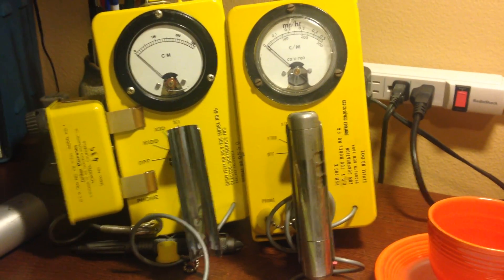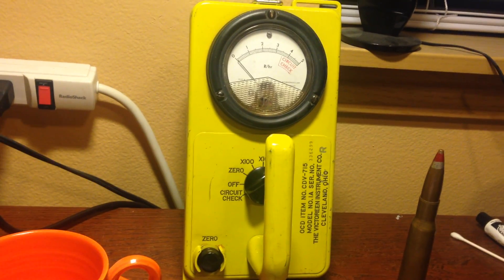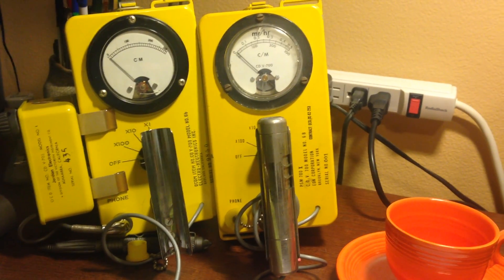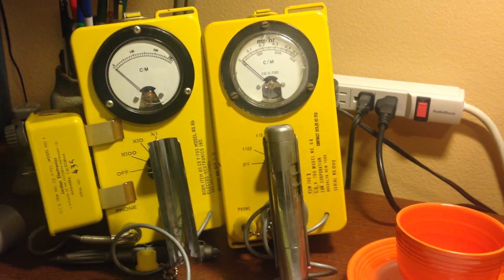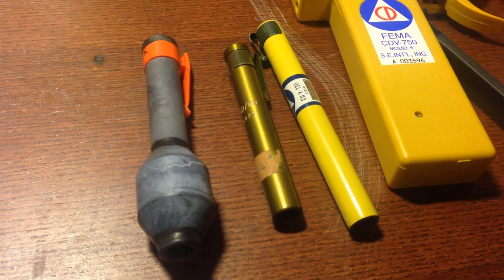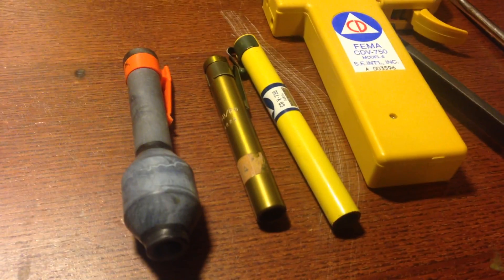If you're looking for a useful meter, avoid the CDV715 rate meter at all costs, unless you're buying it directly from a calibration lab that has put in all brand new electronics. Even then, for the cost, you might as well contact Ludlum Instruments and buy a modern unit. If you want something useful, get a CDV700 — it's a true Geiger counter, pretty cheap, usually under $100. Make sure the seller has tested it beforehand; they all have a check source on the side, so there's really no excuse for not testing it. As far as dosimeters go, the CDV742 is pretty much useless, and I wouldn't recommend the average consumer buying a dosimeter.